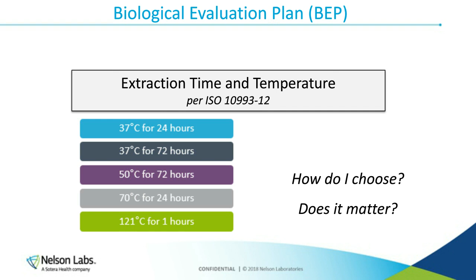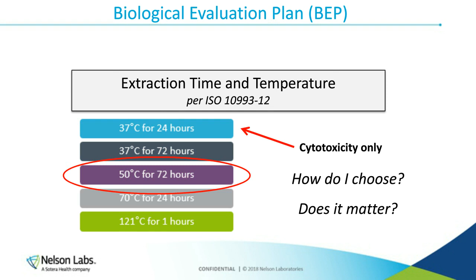justified. So cytotoxicity is typically done for 24 hours. However, the FDA has started to ask that cytotoxicity be done for 72 hours for implants. That's just one of those nuances that needs to be identified up front so that the testing is performed appropriately for the device. Typically, we sit here with 50 degrees for 72 hours. That's most common. So again, keep all of this information in mind to make sure that you're documenting that in your initial risk assessment.